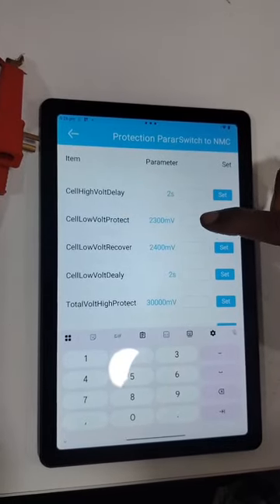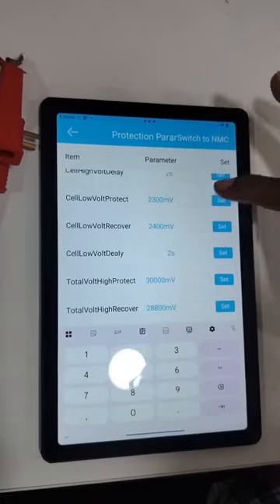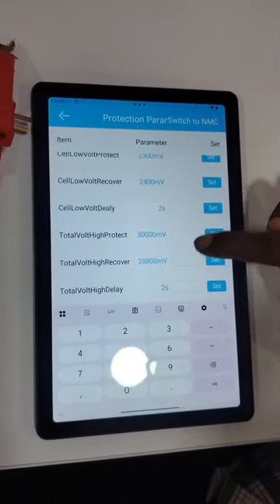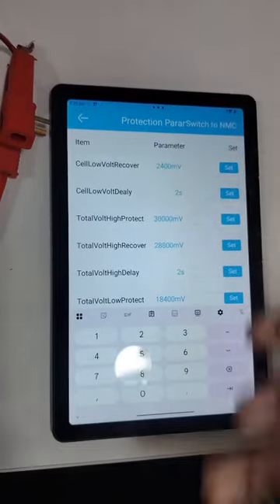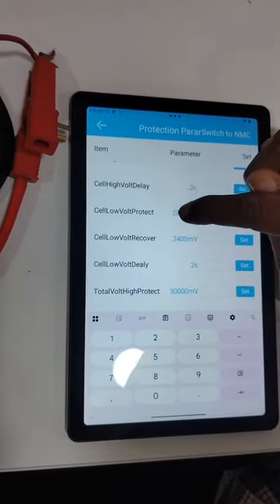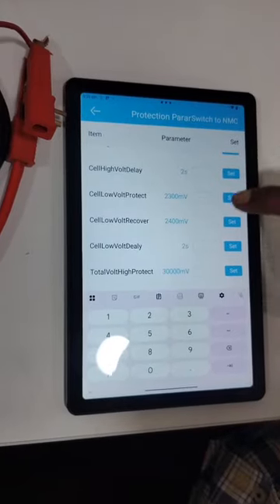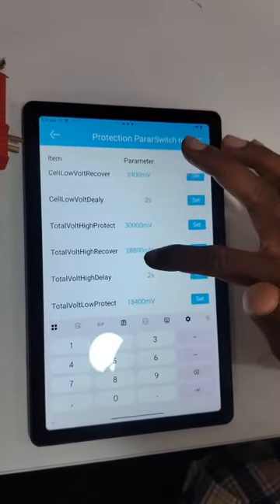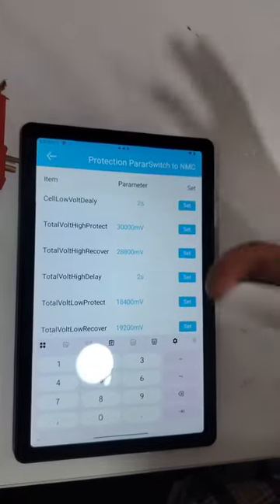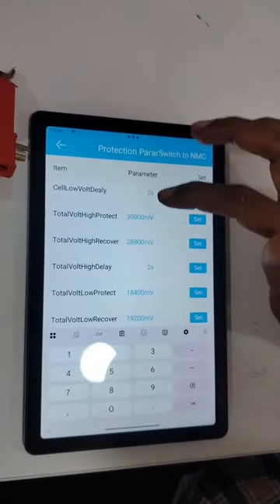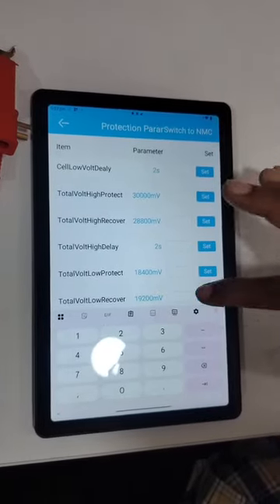low voltage, as I said, is around 2.3 volts, and the recovery voltage after the low voltage return is around 2.4. Again the low voltage delay is around 2 seconds. So what is this delay? Delay means, see, if the voltage is going to the lower voltage side, within 2 seconds it will prevent this particular voltage from going below 2.3 volt, this 2300 millivolt or 2.3 volt. Similarly, high voltage is set to 30,000 for the complete battery pack, and recovery voltage is set to 28,800. Similarly, delay time and all the voltage values we can set here.